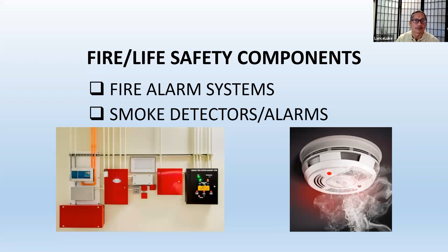And here's the difference: a smoke alarm is a single unit, a single device, and when it sets off, only that alarm sounds. Now, a smoke detector is a series of these devices connected. So when one is alarmed, the other ones do the same thing. So let's say you have a smoke detector in a high-rise building. When that detector goes off, okay, other detectors downstream will go off also. A smoke alarm, you only hear it in one unit. Okay, so that's the big difference.